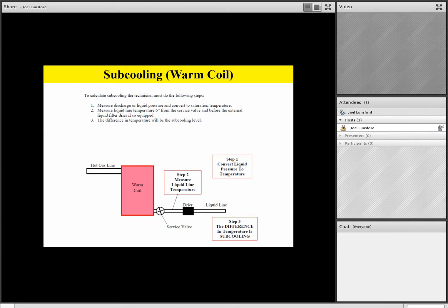Now remember, team, if the subcooling is high, the coil is flooded full of liquid. If the subcooling number is low, the coil is starved. If the subcooling is about 10 to 15 degrees in the cooling mode, we'll consider that normal. If it's about 15 to 25 degrees in the heating mode, we'll consider that normal. So this time, let's go ahead and do some subcooling practice. Have your pressure temperature chart handy as we do the subcooling practice on the warm coil.